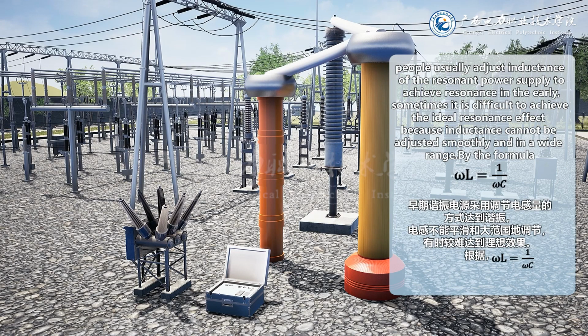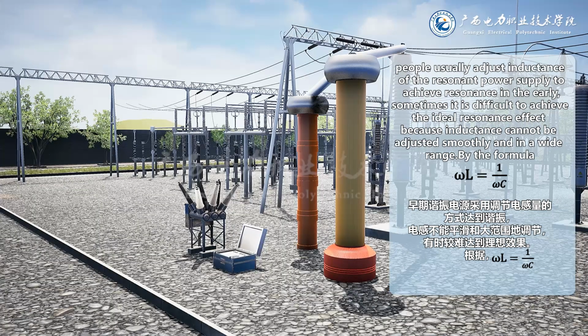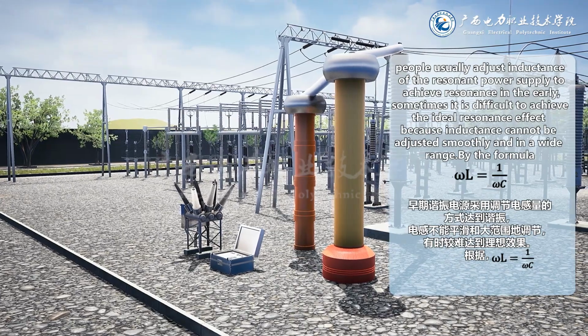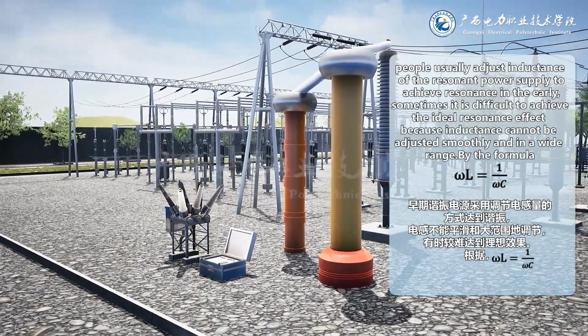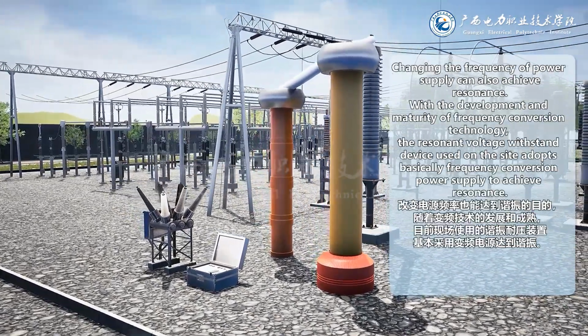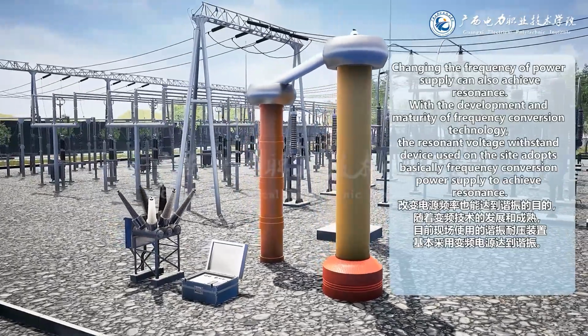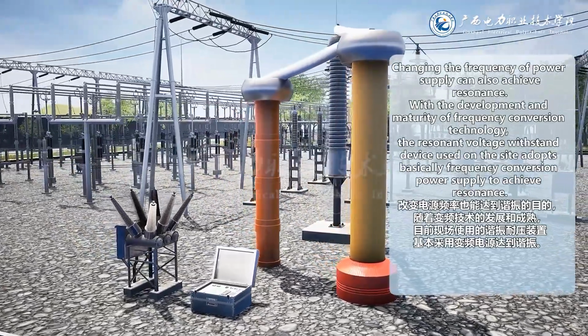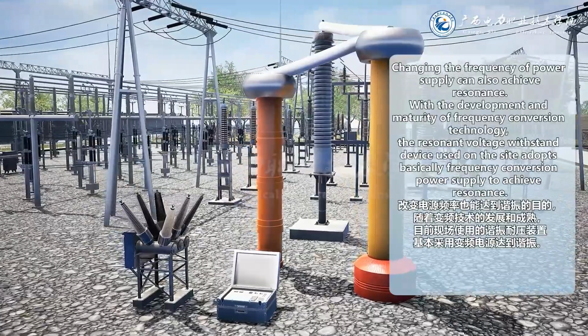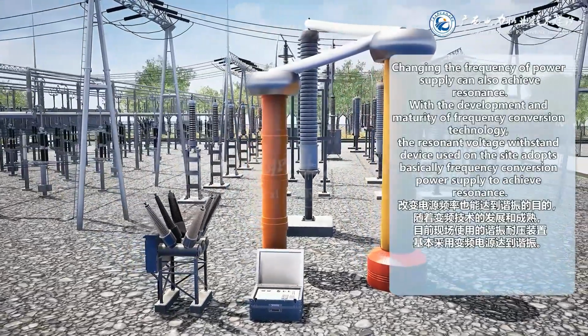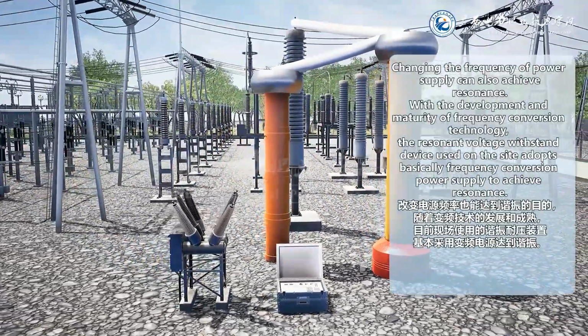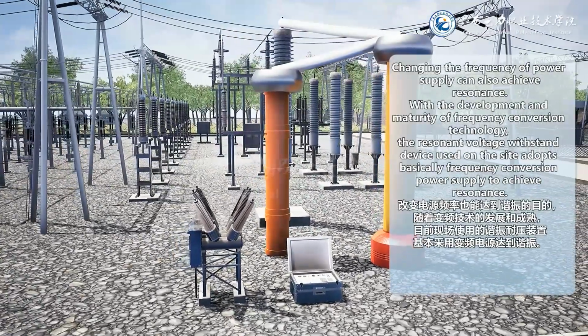People usually adjusted the inductance of the resonant power supply to achieve resonance in the early days. Sometimes it is difficult to achieve the ideal resonance effect because inductance cannot be adjusted smoothly and in a wide range. By the formula, changing the frequency of the power supply can also achieve resonance. With the development and maturity of frequency conversion technology, the resonant voltage withstand device used on site basically adopts a frequency conversion power supply to achieve resonance.